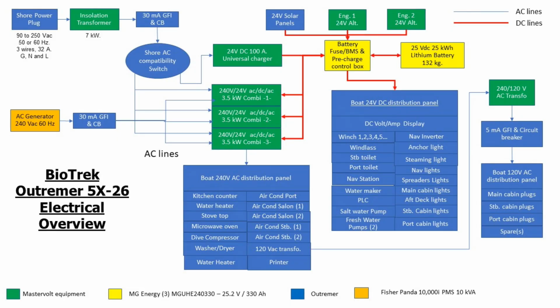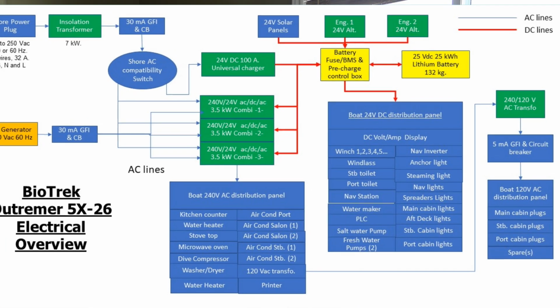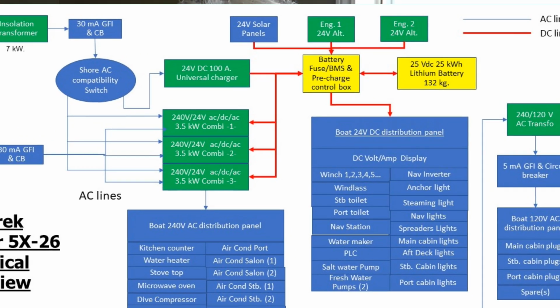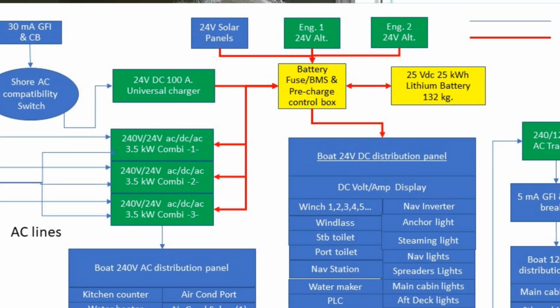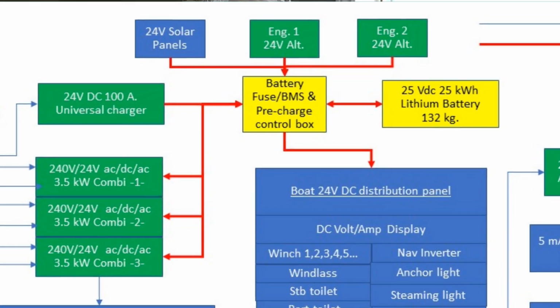So if you look in the first blue box there, one which is powered directly by the BMS, which is that square-ish yellow box there in the middle, which, as I said, is bi-directional with the battery because it's reading from the battery, but it's also sending commands back to the battery as far as balancing it between the cells and these different things. As I said, the BMS has the authority to open and close the contactor, even though we can do it with the CAN bus commands.